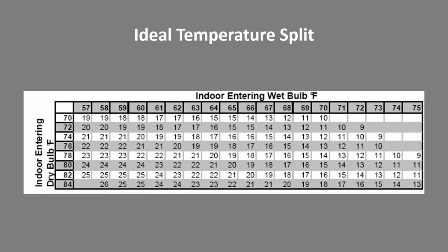So all of us have probably heard that, hey, that air conditioner is getting us a 20-degree split. It's working just fine. And for large parts of the year in the Northwest climate, that's true. Say we have an indoor dry bulb going into the indoor coil at 76, and the indoor wet bulb is 62. Yep, guess what? You have the ideal temperature split.